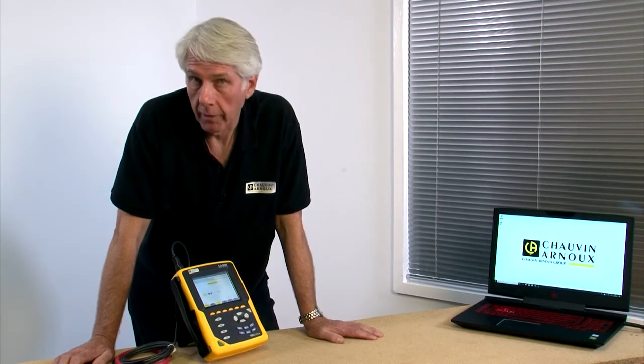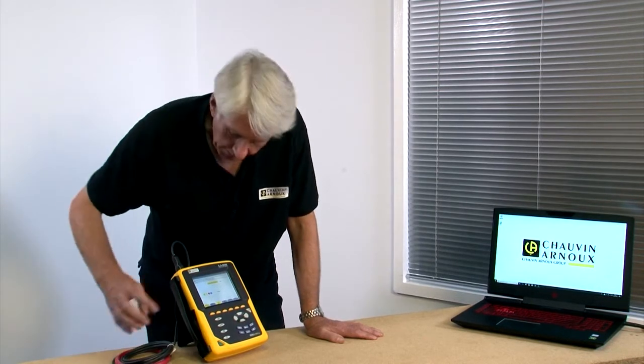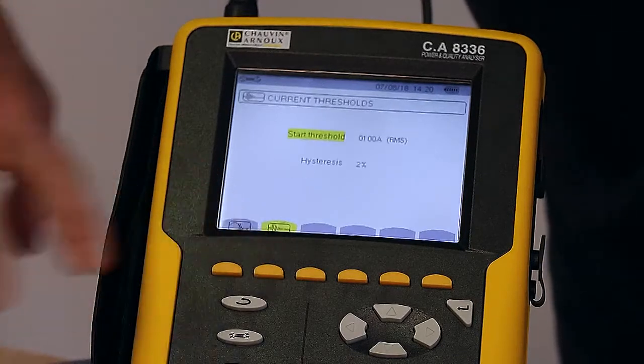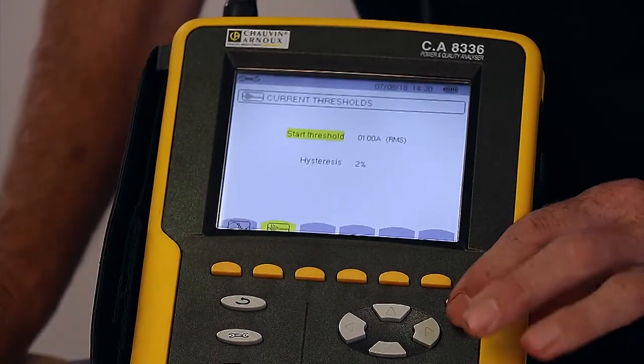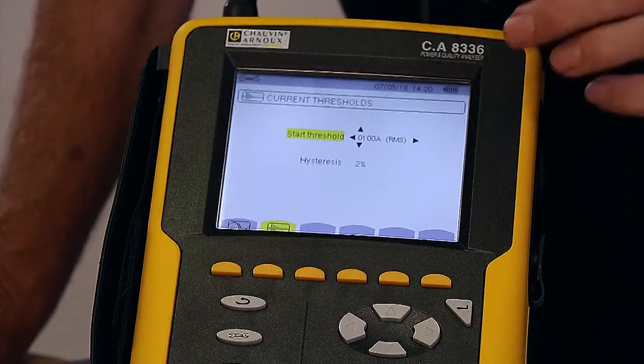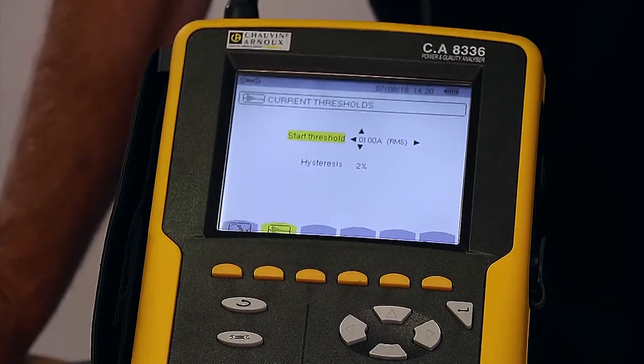Within capture mode, we can also set up the parameters for motor inrush current. So by pressing the fast button here for inrush, selecting Enter, we can set a current limit above which inrush currents will be measured.